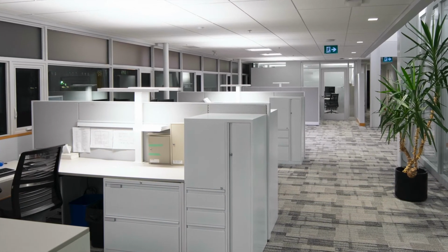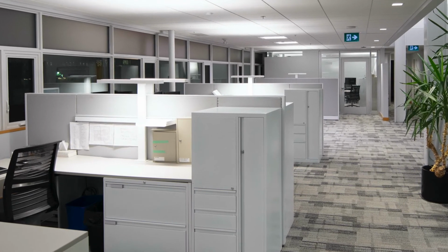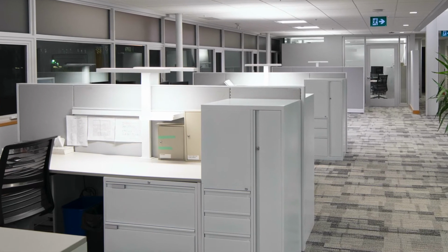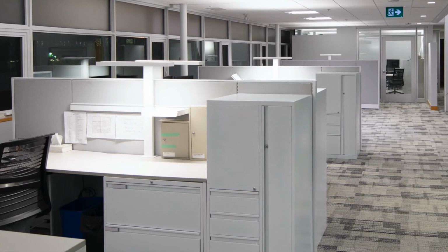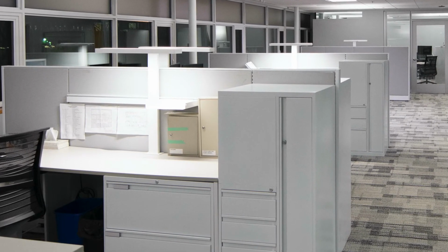Desk-mounted 2-circuit direct-indirect luminaires illuminate office spaces. Occupancy sensors and daylight harvesting control ambient uplight. Task lights are occupant-controlled with under-desk vacancy sensors. At night, lighting is soft, comfortable, glare-free, and effective for tasks.